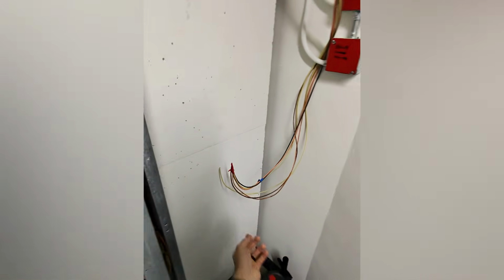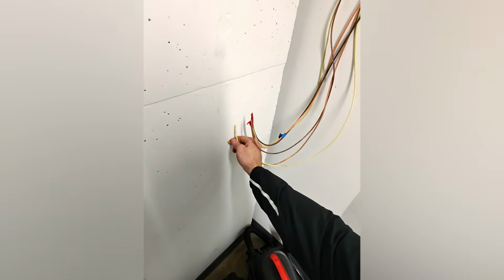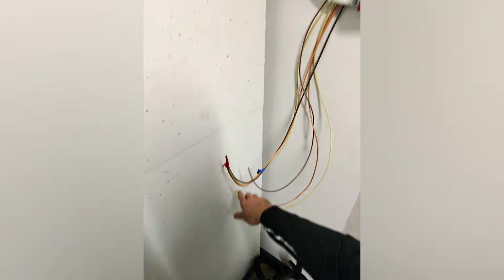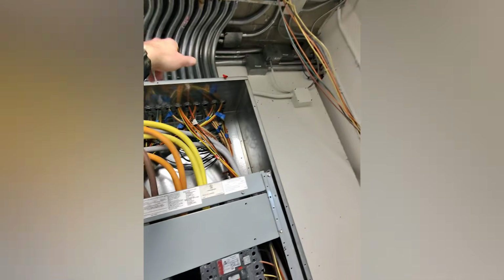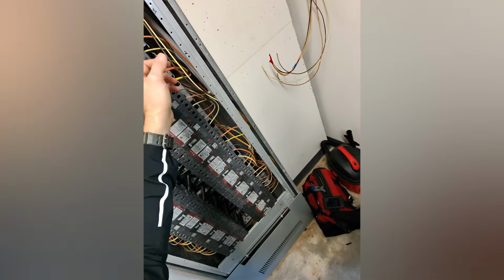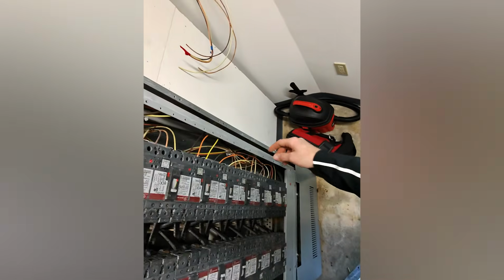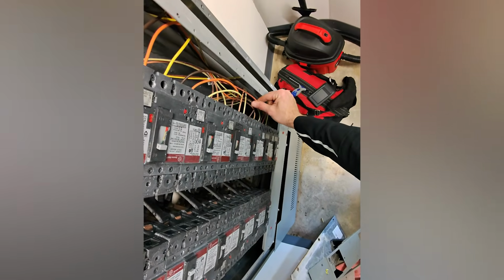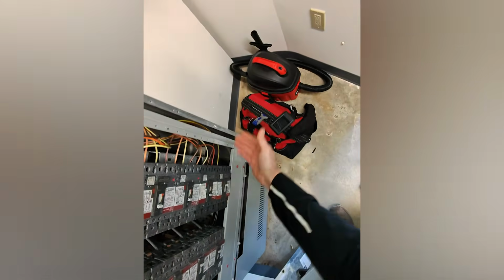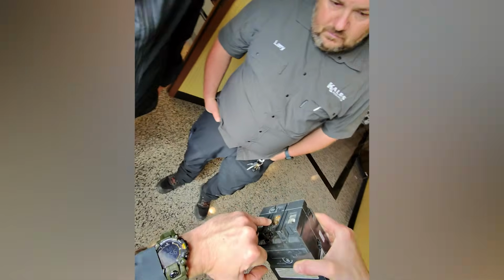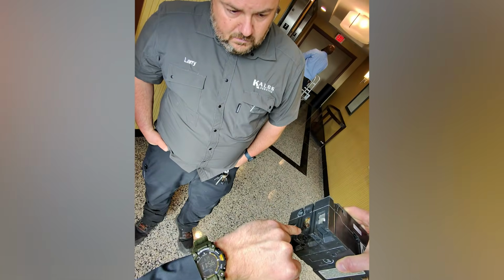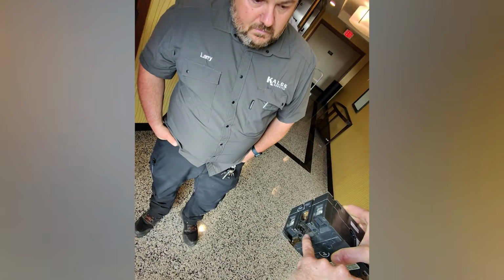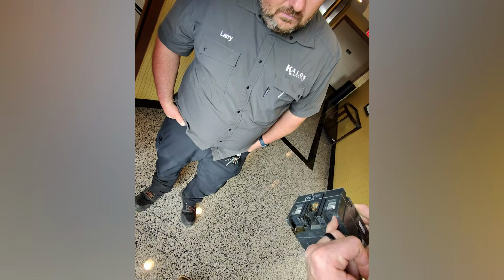with the water dripping down the wires, you can see the water on the wall now from the wires. Water dripping in the wires, down into the panel, going down the wire here, which is where you can see these little snail trails, then into the breaker itself to where it failed electrically. It came down the wire, with the breaker being this way. It puddled and pooled right here where you can see it, right? And then when it pooled here, the water got high enough to come across the backside where it's not sealed, because this is a loose block.